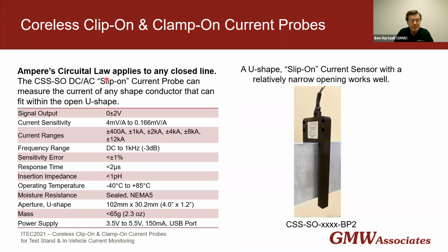Now, because the circuital law can apply essentially to any shape, we can use it on a shape like this, which is a U shape that will slip over a bus bar. And this one can be used to measure currents on a bus bar, but it can also be used to measure, say, a cable that's in any position within the U. And this looks something like this. So it's a sort of tuning fork shape. It's very slim in the axial direction, so it can be slipped into a confined space. And again, it's very light.